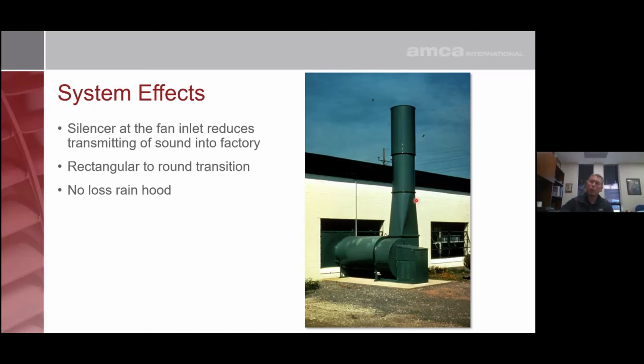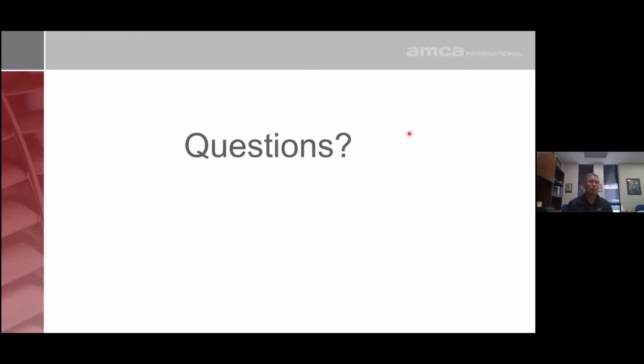Straight run of ductwork, and then we have what we call a no loss rain hood at the discharge of the fan that does two things: it prevents rain from getting back into the fan, and there are no losses associated with this appurtenance during performance. So it's a really nice device for discharging air to atmosphere without any losses associated with that fan. Any questions that have come up to this point on system effects?